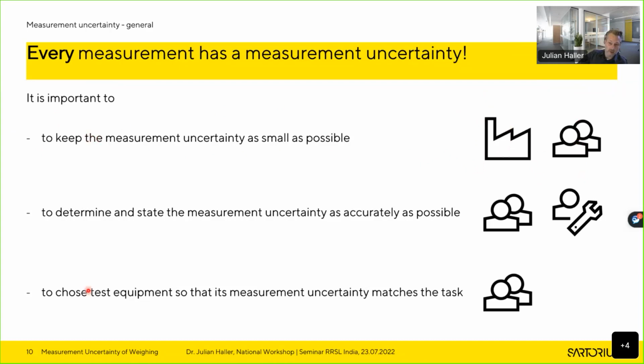It is further important then to determine and state the measurement uncertainty as accurately as possible. And this generally is also, and this is a surprise to many of our users, actually the task of the user of the measuring instrument. What we can provide, and actually we do that via our service department, is to provide respective help for the user, but generally and formally, it's the task of the user to determine and state the measurement uncertainty of his instrument. And of course, usually in the beginning, it is important to choose test equipment so that its measurement uncertainty matches the task. And this is, of course, again, the responsibility of the user.